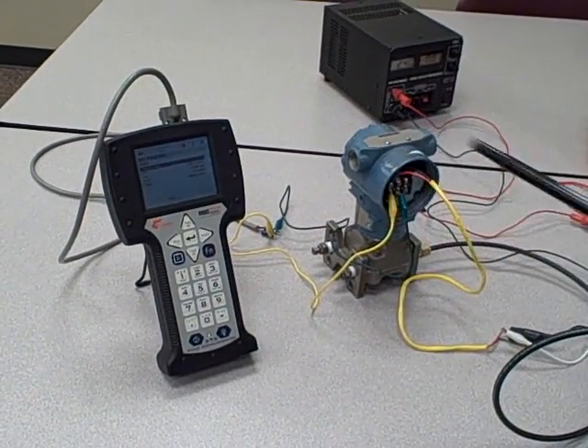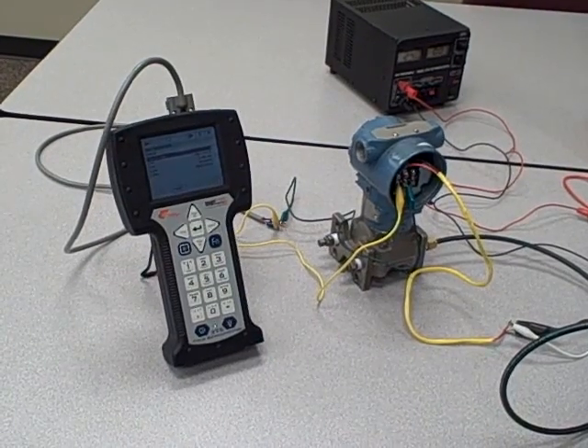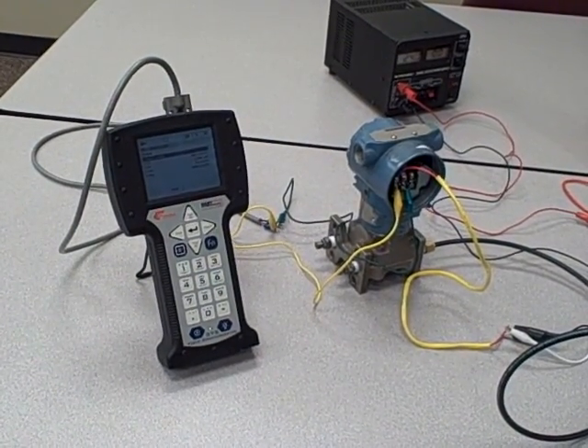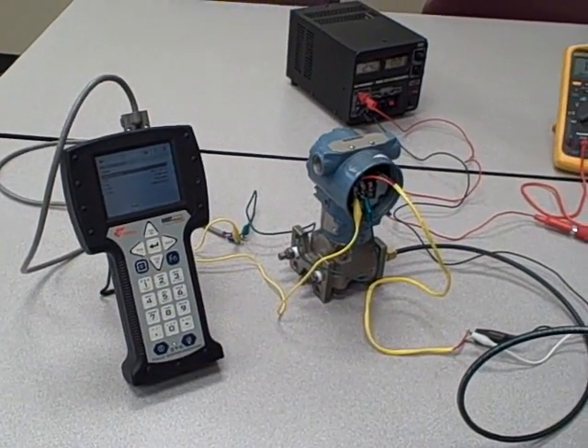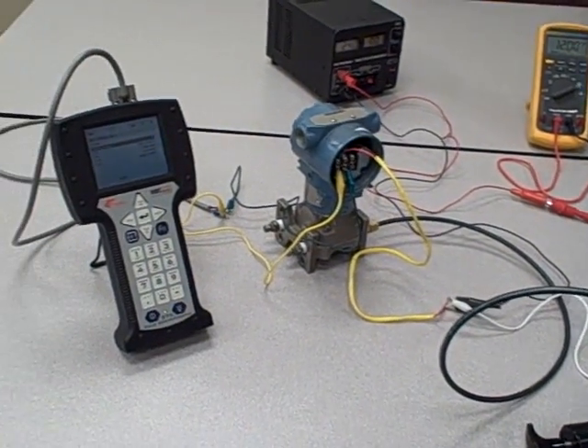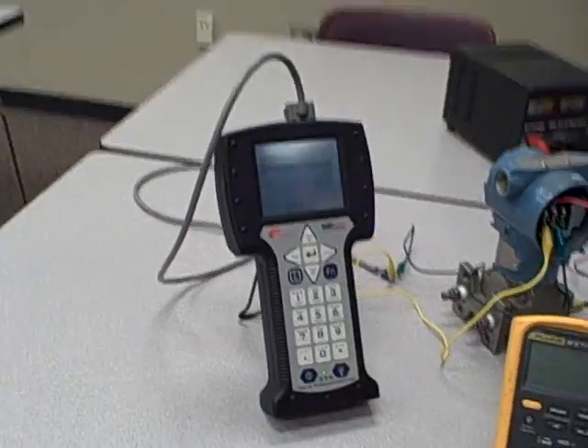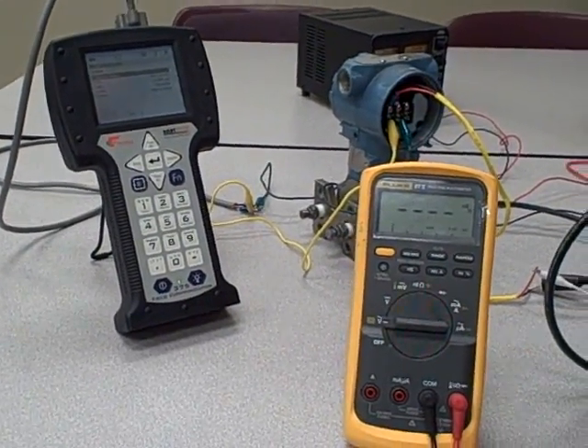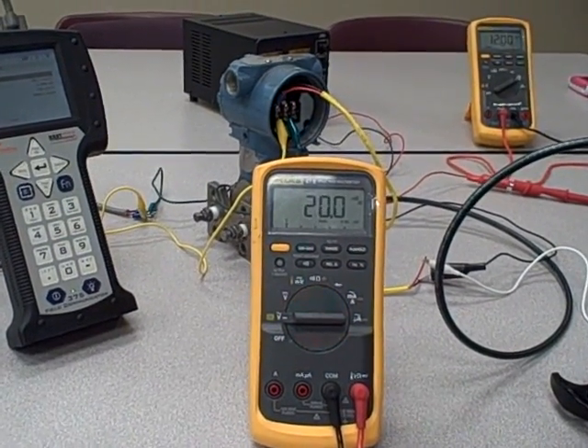And indeed, HART itself is not exactly a new technology. It's a 1980s era technology, but it's still in very wide use. What I'd like to do first is show what the HART communication signals actually look like using a meter. An oscilloscope would be an ideal tool for this, but for right now, I'll demonstrate how to use a normal Fluke meter to do the measurements.